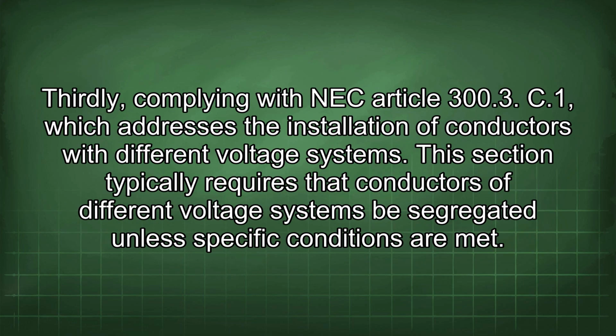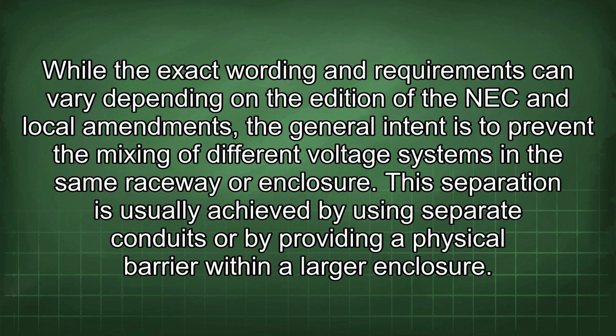Thirdly, complying with NEC Article 300.3(C)(1), which addresses the installation of conductors with different voltage systems. This section typically requires that conductors of different voltage systems be segregated unless specific conditions are met. While the exact wording and requirements can vary depending on the edition of the NEC and local amendments, the general intent is to prevent the mixing of different voltage systems in the same raceway or enclosure. This separation is usually achieved by using separate conduits or by providing a physical barrier within a larger enclosure.